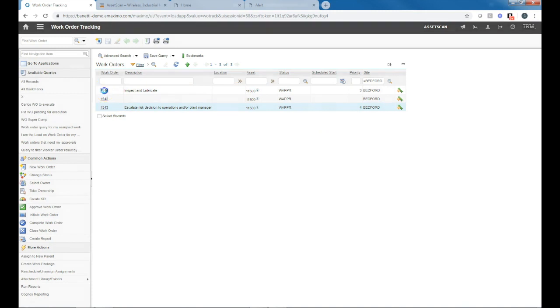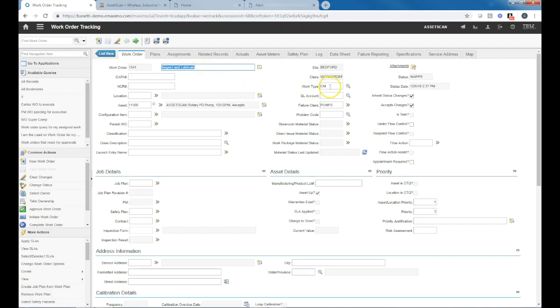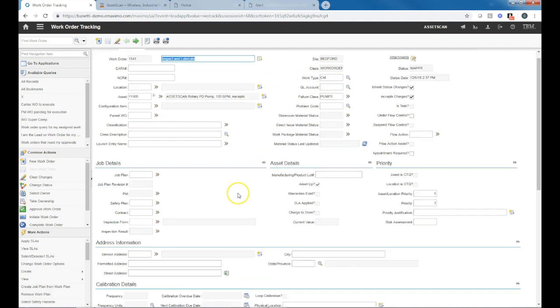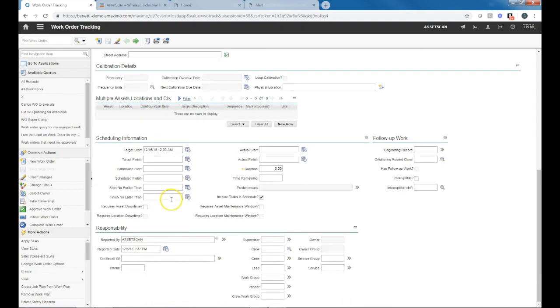If we drill into this, this was generated off the ultrasonic minor alert and the prescriptive task there is to inspect and lubricate. This is generated automatically in the description. The work type of corrective maintenance is generated, a target start date out 10 days. So again, allowing the maintenance organization time to plan and schedule. And you can see that AssetScan generated this and at what time.